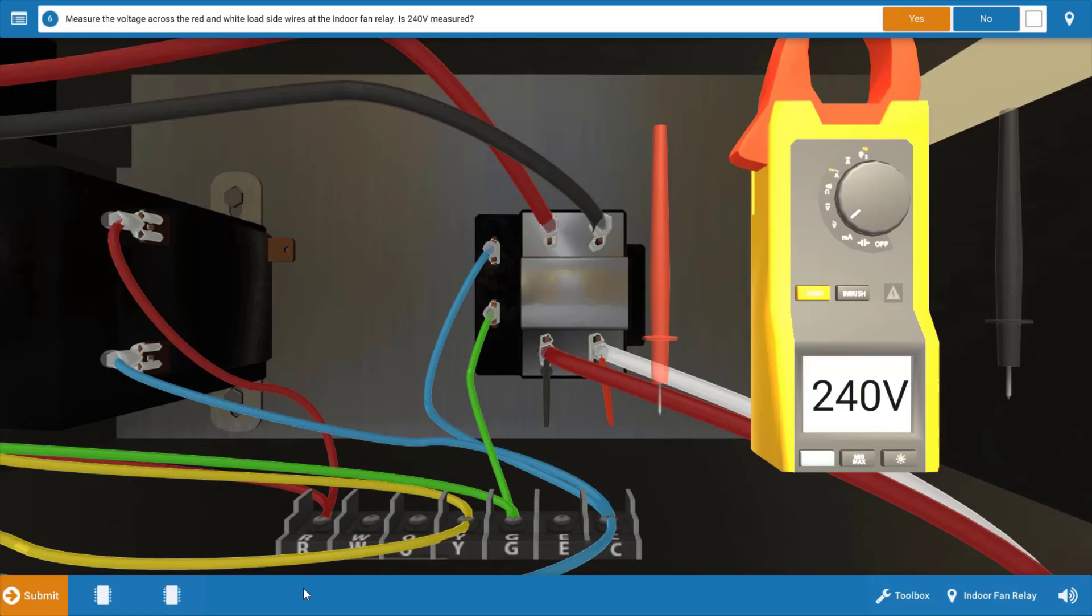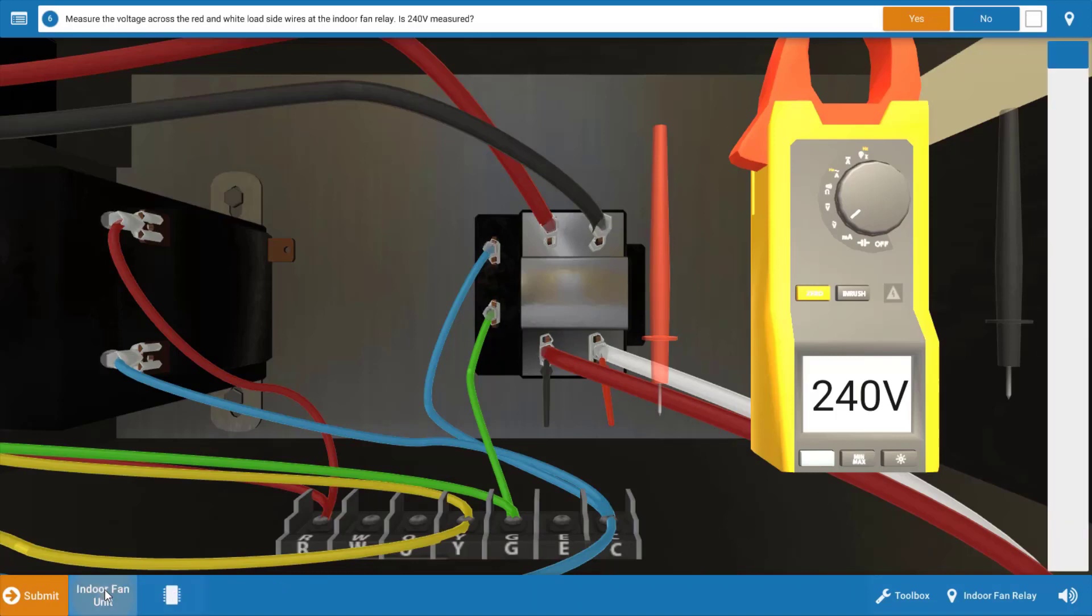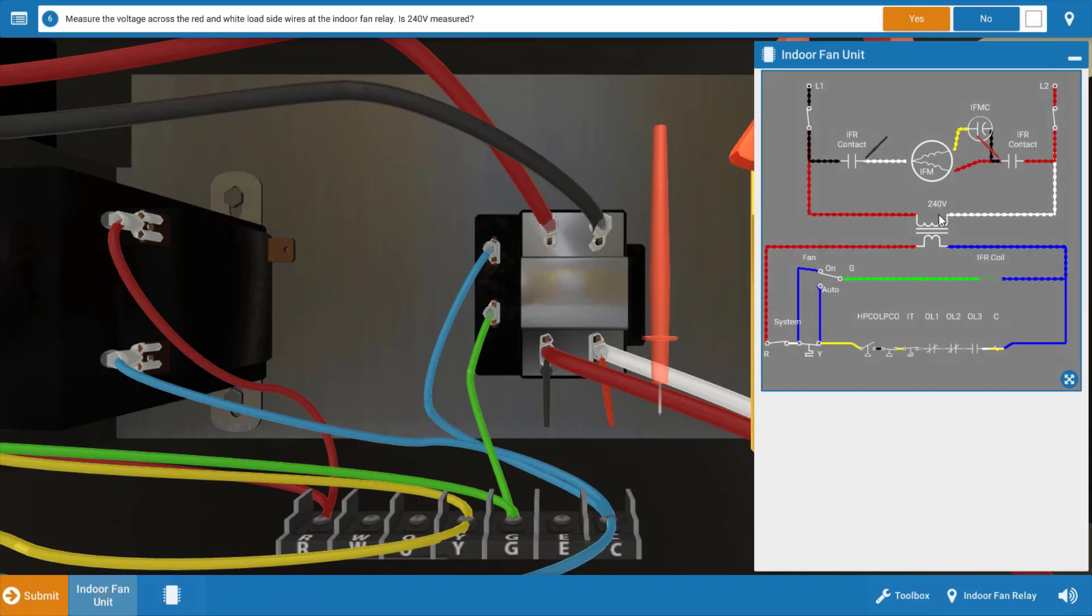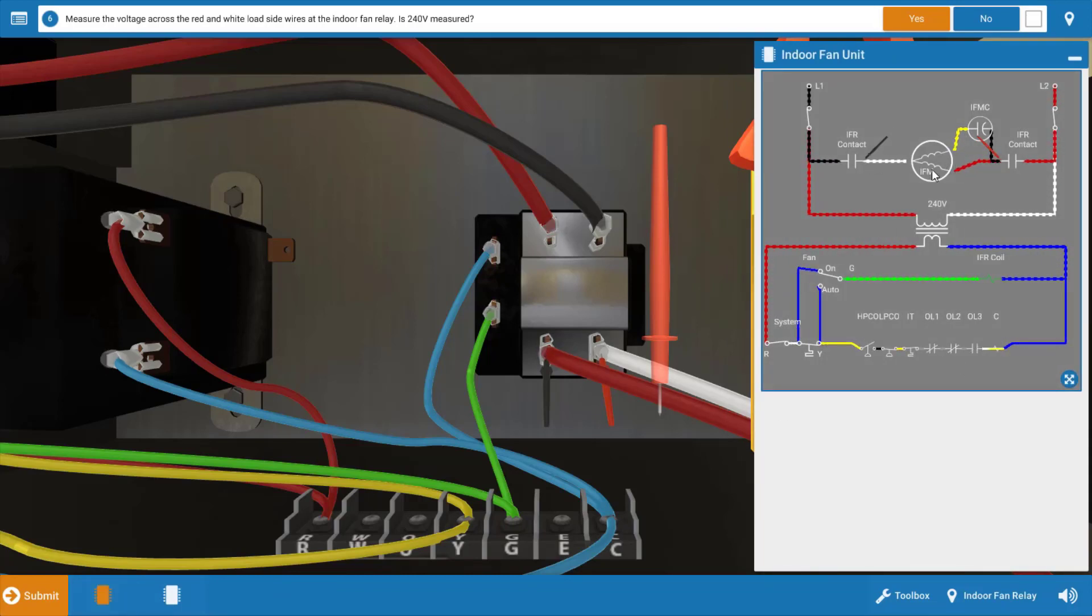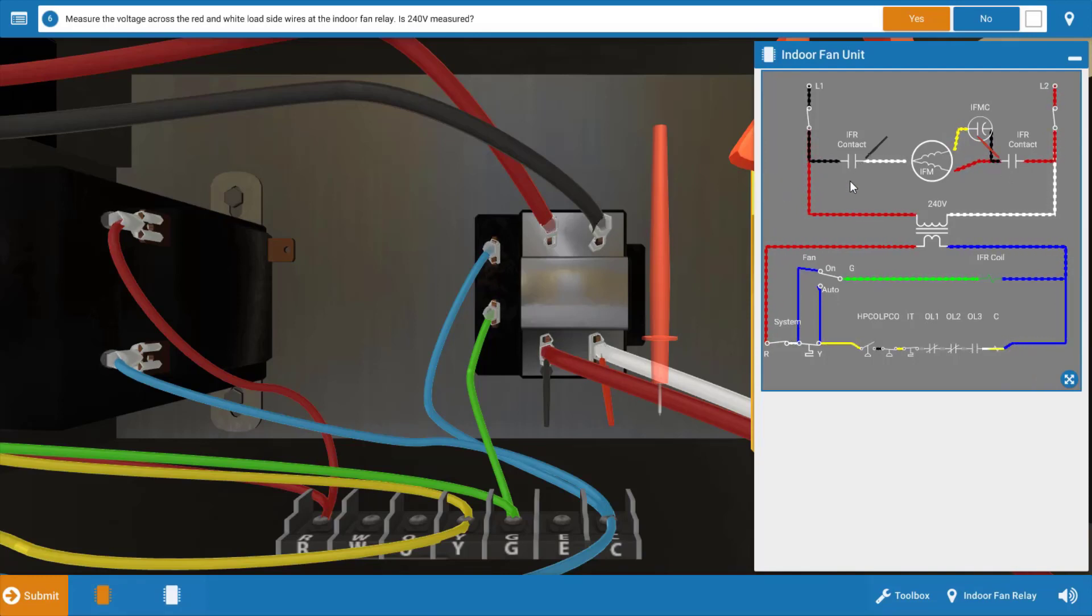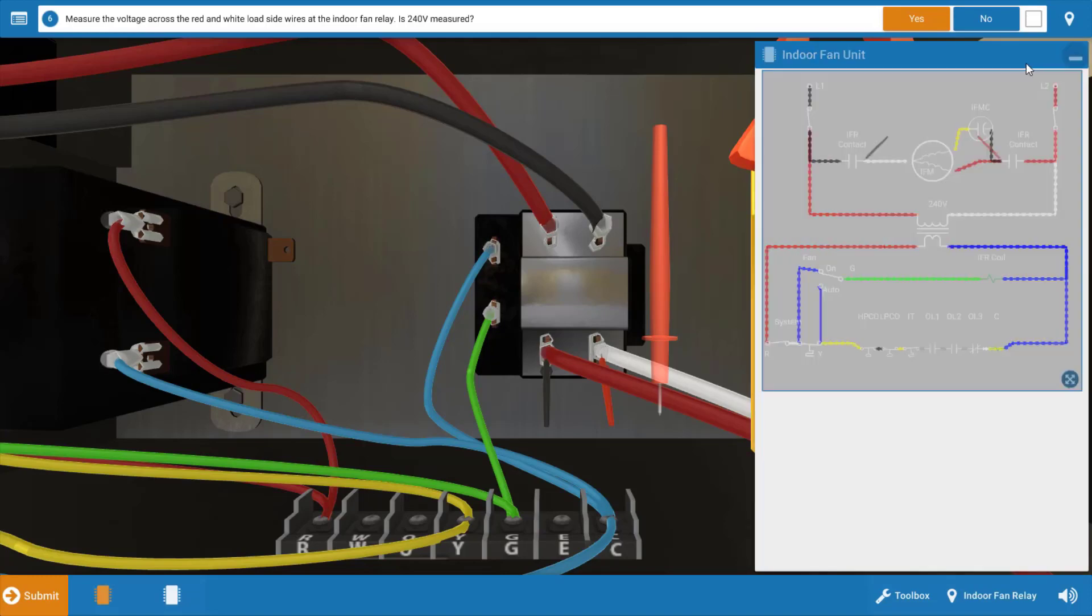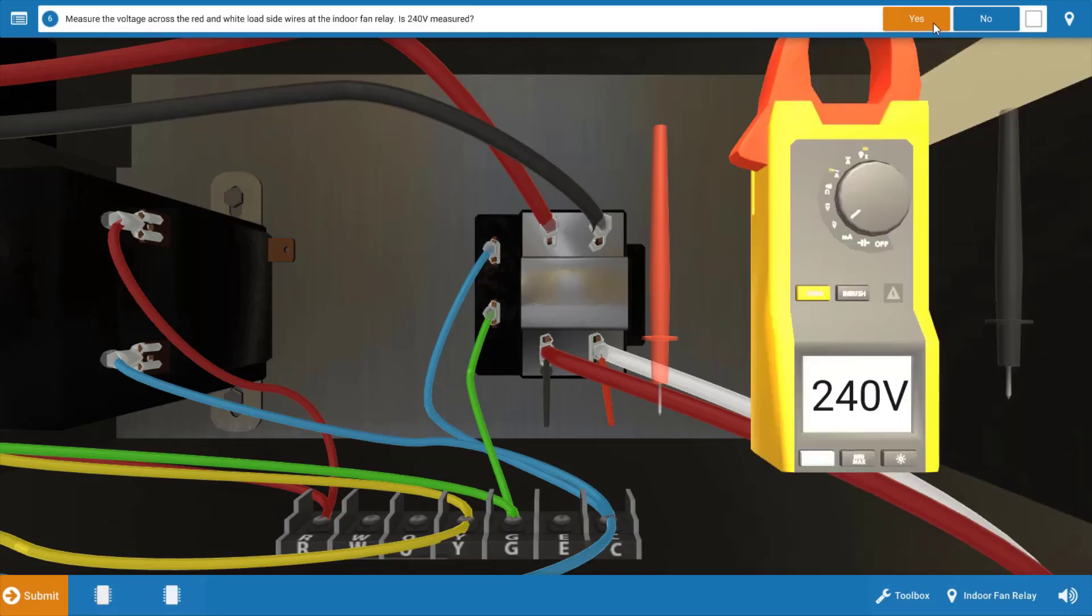If you're confused, let's go back to the wiring diagram. If we look at the placement of our meter leads here on the diagram, we've verified voltage at this point. This verifies that these contacts are closed. So now we've narrowed it down to either the indoor fan motor or the capacitor.